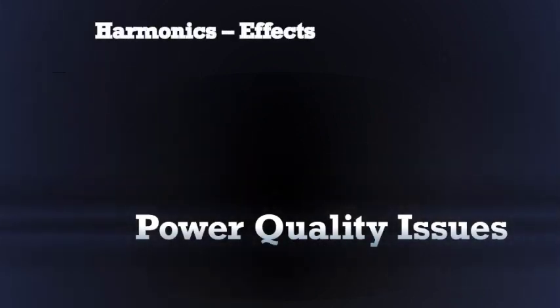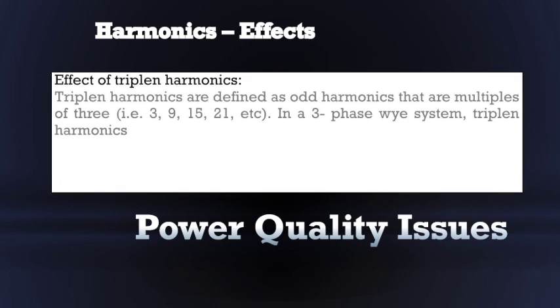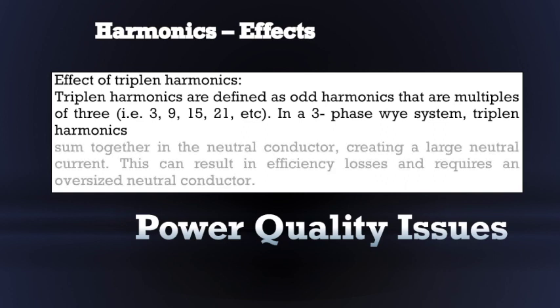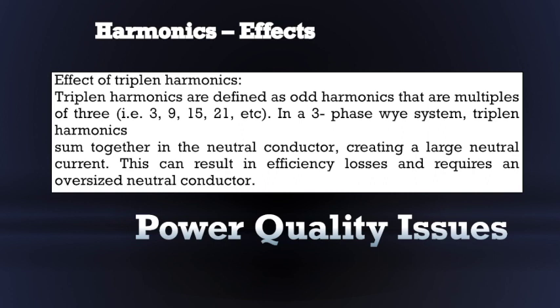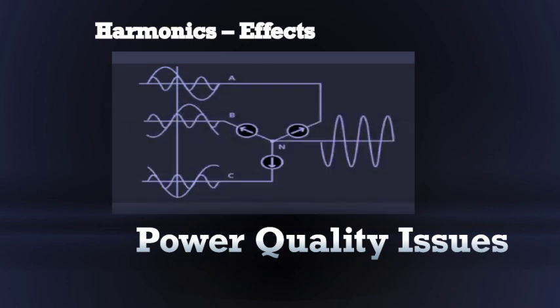What are the effects of triplen harmonics? Triplen harmonics are defined as odd harmonics that are multiples of 3. That is 3, 9, 15, 21, etc. In a three-phase star system, triplen harmonics come together in the neutral conductor, creating a large neutral current. You can see the figure. This can result in efficiency losses and requires an oversized neutral conductor.